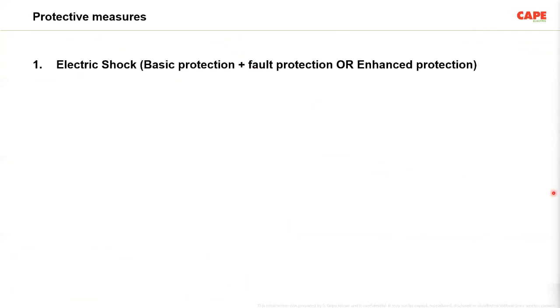For an electrical installation, the protective measures required are categorized into 4: electric shock protection, protection against thermal effect, protection against overcurrent, protection against over voltage. So basically, protection against electric shock is to ensure that people and animals are not getting shock. It is achieved by 2 protective measures called basic protection and fault protection. This also can be done by an enhanced protective measure. These are a little bit technical words, but for electrical engineers, sometimes these are useful to understand.